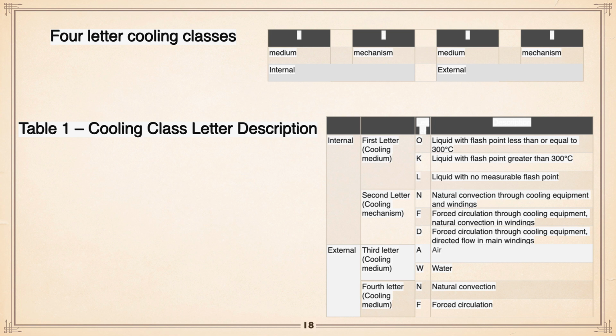Natural convection through cooling equipment and windings, or you can get into different forced variations again. So ON is fairly common. On the external, in other words, the outlet side of the thing, the service side, you've got your equipment side. Basically, we talk about AN. A is air, W would be water, which is rare, and the fourth letter is how it's actually being cooled. So ONAN, the last N would be natural convection, just cooled by radiating heat to the air. That's why you see transformers so often with fins on them.